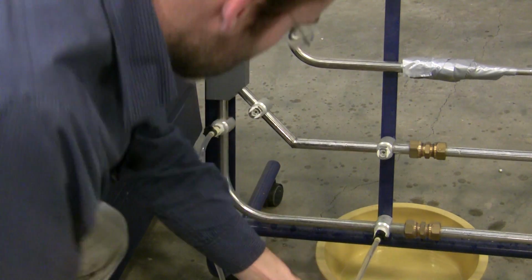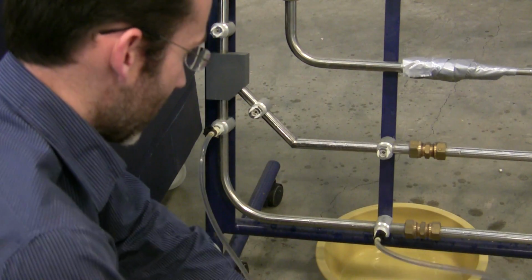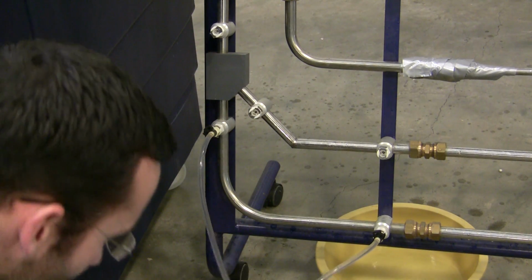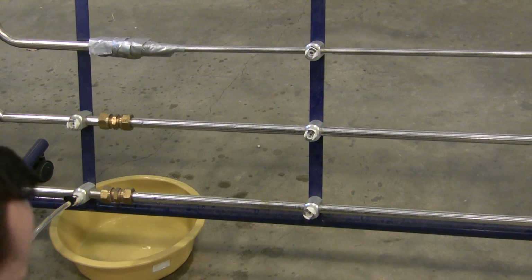All right. I'll inspect to see if there's any air in the lines, and it seems like I didn't get any air in the lines, so I'm in good shape there. Let's again get some pressure measurements. I'm going to mop up a little bit more of this overspray, particularly off the pressure instrument.